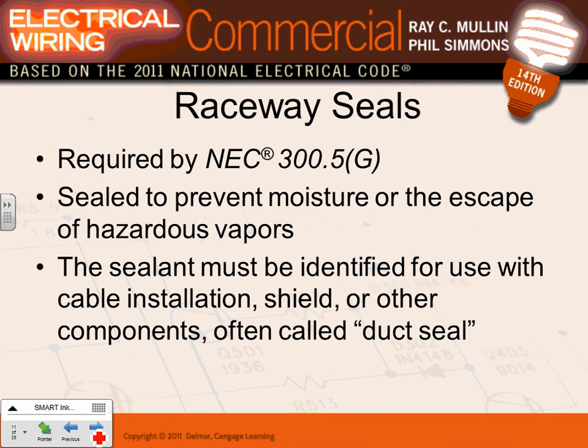Raceway seals: if you bring a conduit between two different temperature zones, you have to seal. You seal between outside and inside. In 2011 they added a requirement to also seal if you're coming from underground into the building with a feeder, branch circuit, or service. Why? Because they got tired of creatures coming through the conduit into the switchgear and creating arc flashes. So if you have PVC conduit coming into the bottom of the switchgear, you have to seal as you enter.